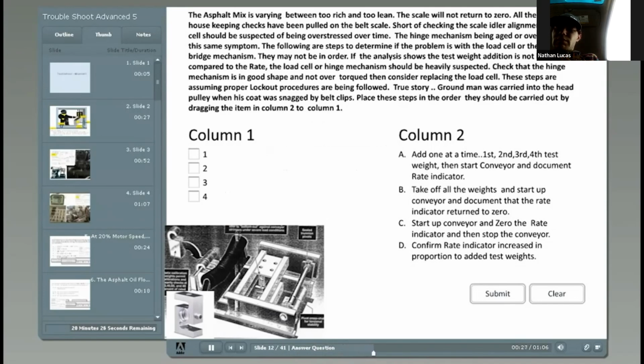The following are steps to determine if the problem is with the load cell or the weighbridge mechanism. They may not be in order. If the analysis shows the test weight addition is not linear compared to the rate, the load cell or hinge mechanism should be heavily suspected. Check that the hinge mechanism is in good shape and not over-torqued, then consider replacing the load cell. These steps are assuming proper lockout procedures are being followed.